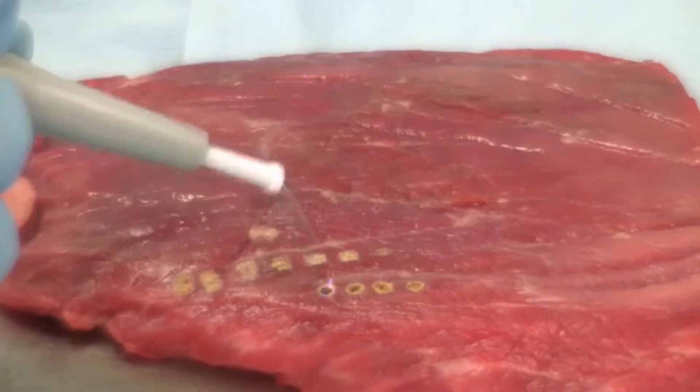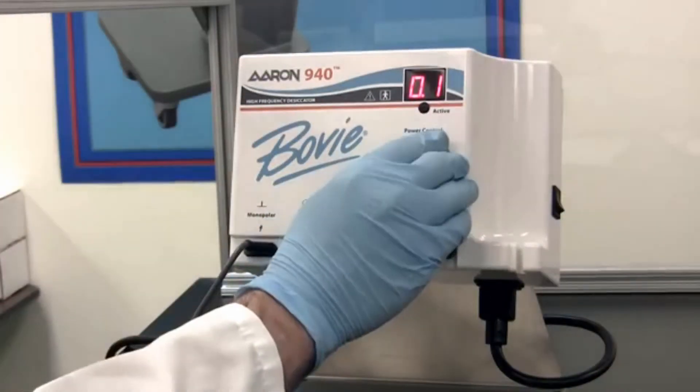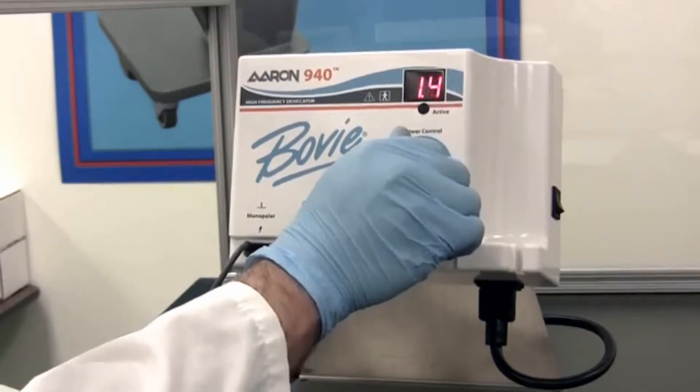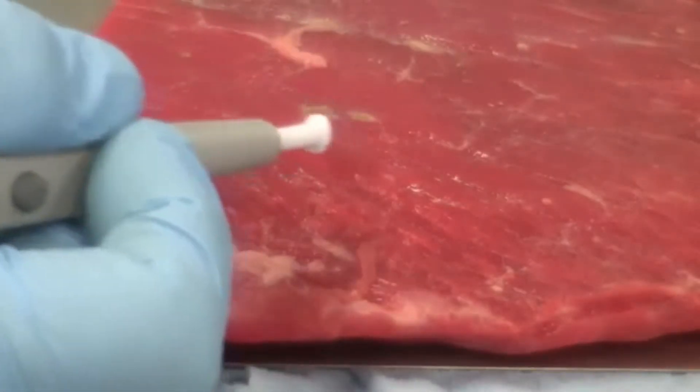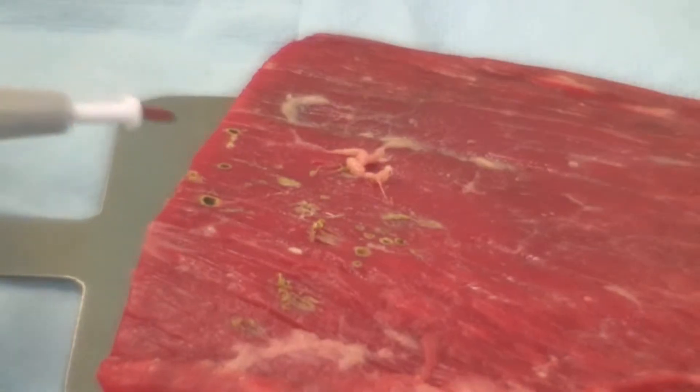You need to avoid applying too much power to the tip. Be sure to adjust the power conservatively at first. As you use the Aaron 940 desiccator for a particular procedure, you will become accustomed to the settings you need to use.